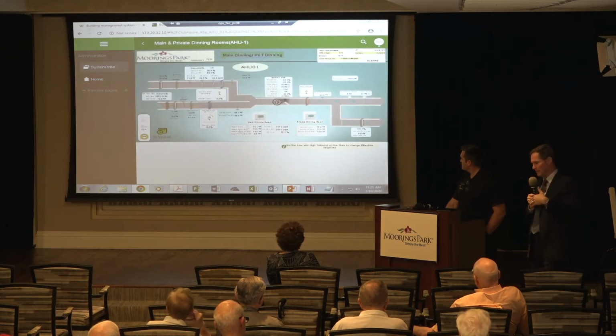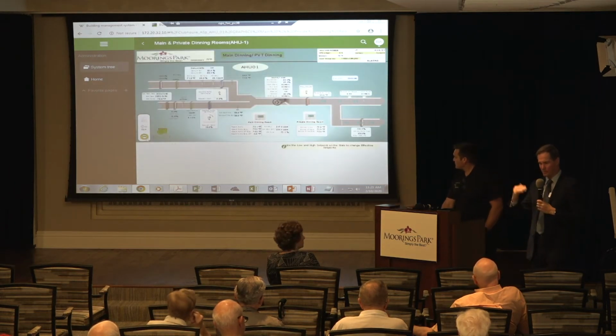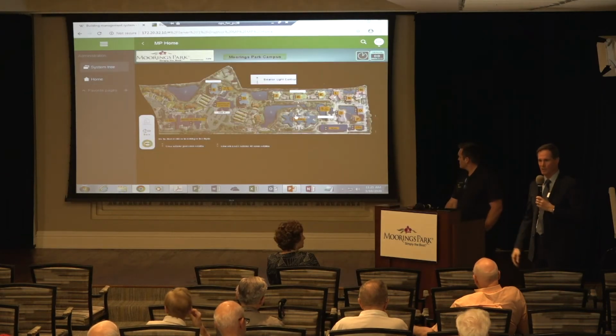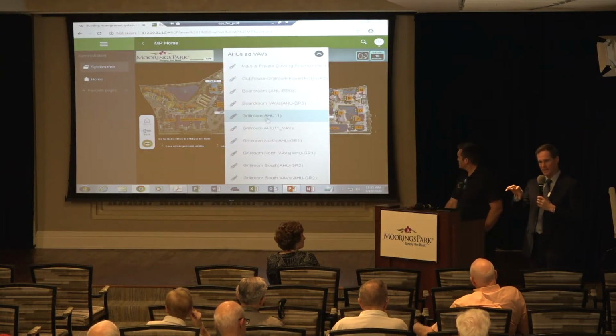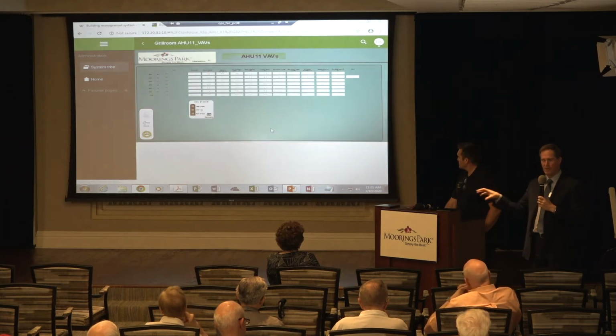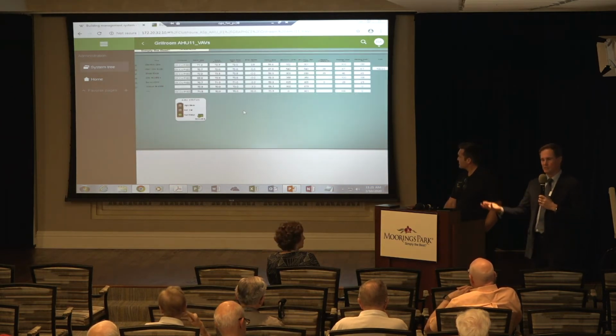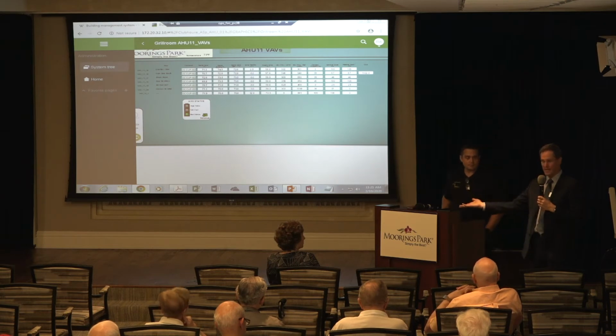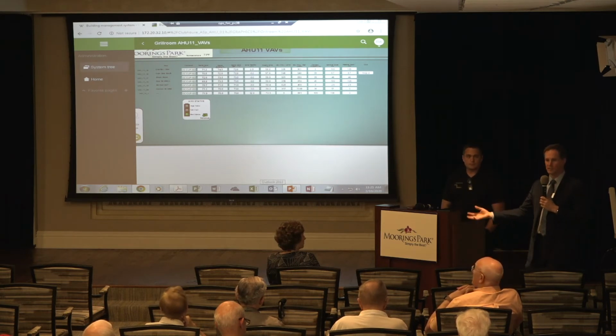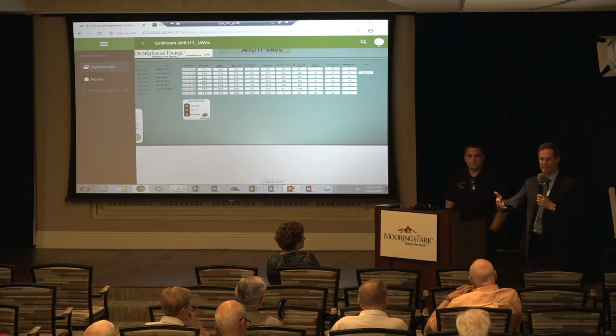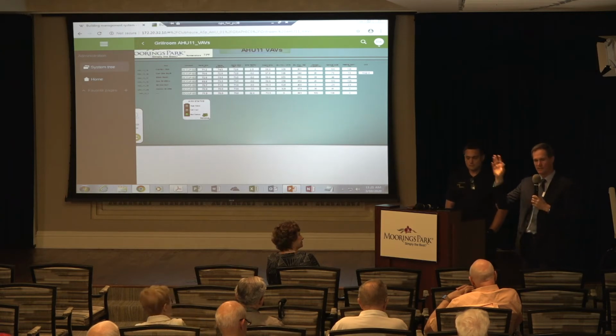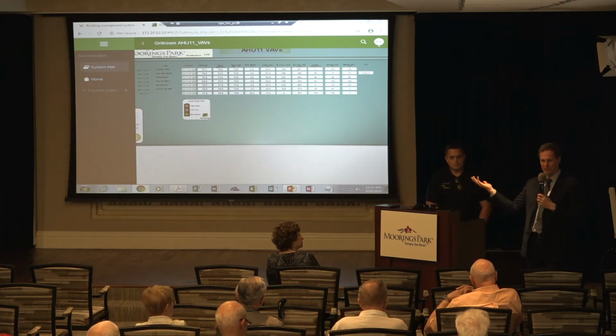Part of our plan — we're starting to work with Future Controls for our capital requests in '21 — is identifying those assets that are not in the system that we want to be able to see. So, for example, I can't see this room right now, so that's potentially an add for '21. In Chateau, I can't see the hallways, so space temperature in the hallways — because if I know the Cypress Wing hallway is down, then I probably know that an air handler is down.